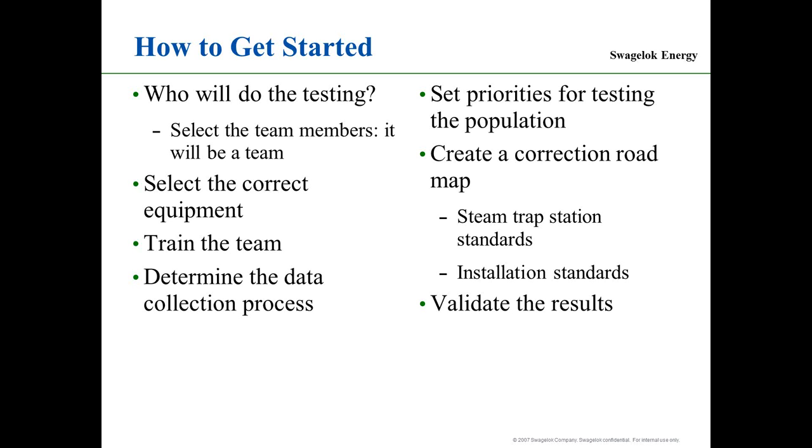Typically not, because the 400 PSI steam trap is discharging into a flash recovery system. And, you know, I'll give you an example. I went to Arkansas, and the plant called me there and said our losses are $2.1 million a year. And when I finally went through the report that was done by an outside firm, savings was only like $80,000, because the high-pressure steam traps were discharging into a flash system. So if the steam trap is blowing through, it's just going to back down the PRV valve a little bit. So understanding the dynamics of the system to set your priorities. So make sure you have understanding, and steam balance is a great way of doing that.